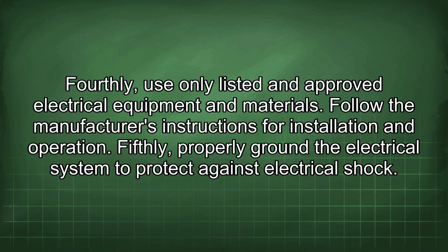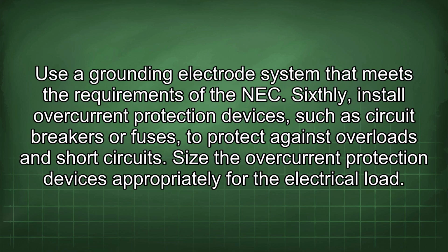Fifthly, properly ground the electrical system to protect against electrical shock. Use a grounding electrode system that meets the requirements of the NEC. Sixthly, install overcurrent protection devices, such as circuit breakers or fuses, to protect against overloads and short circuits. Size the overcurrent protection devices appropriately for the electrical load.